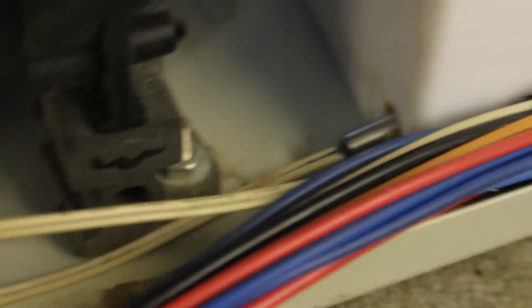Again, that's really difficult for me to get you in there. There's a couple of switches, thermally operated switches that are bonded to the side of the tank. They provide the control signal for an over temperature alarm, and the actual temperature is monitored by this little sensor here. I think it's just a thermistor that's buried in the bottom of the tank.